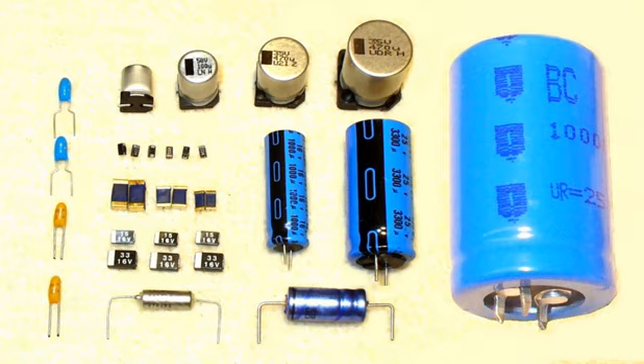During charging, the voltage across each of the capacitors connected in series is proportional to the inverse of the individual capacitor's leakage current. Since every capacitor differs a little bit in individual leakage current, the capacitors with a higher leakage current will get less voltage. The voltage balance over the series-connected capacitors is not symmetrical. Passive or active voltage balance has to be provided in order to stabilize the voltage over each individual capacitor.